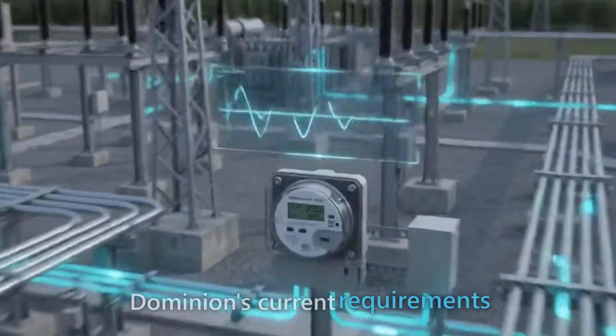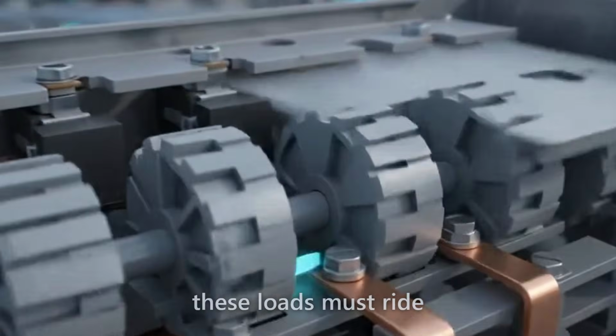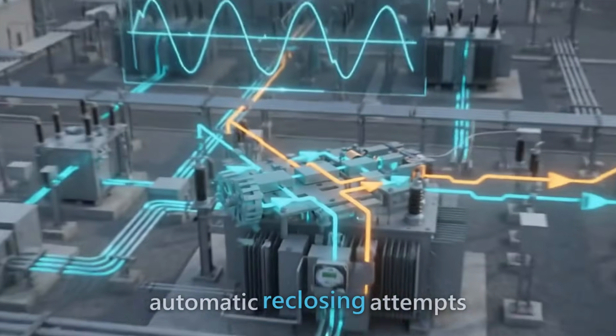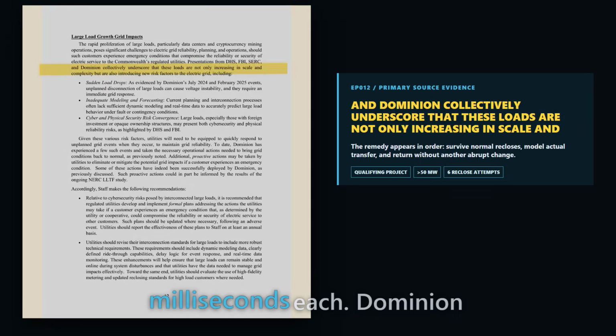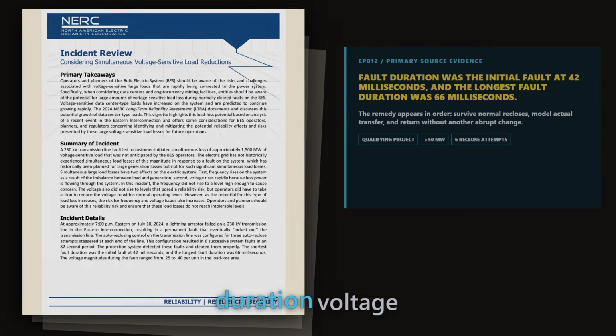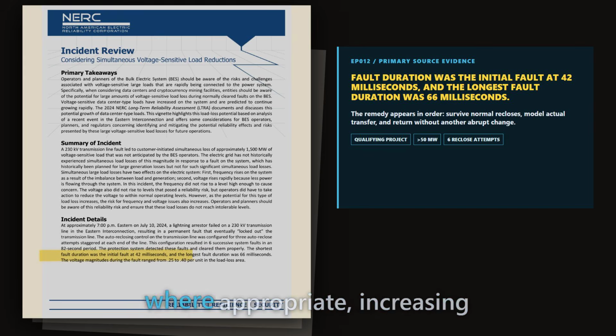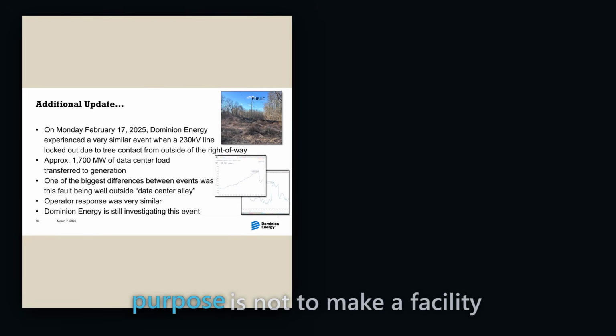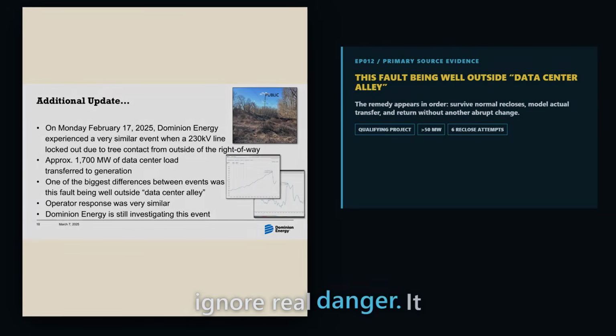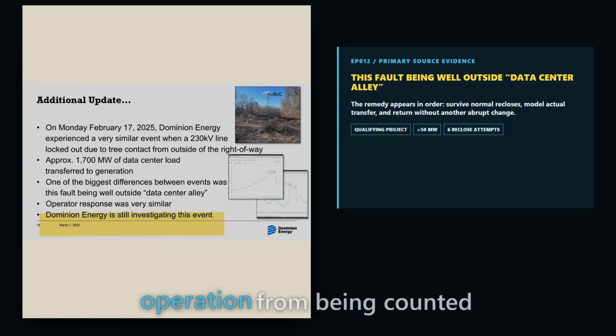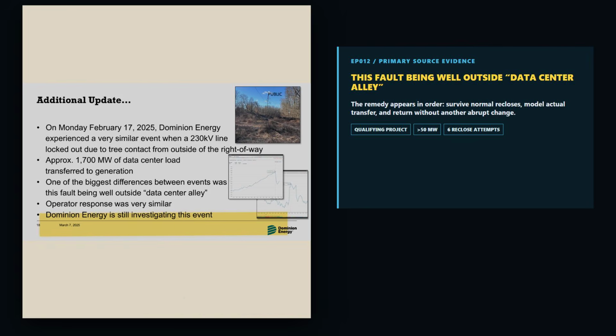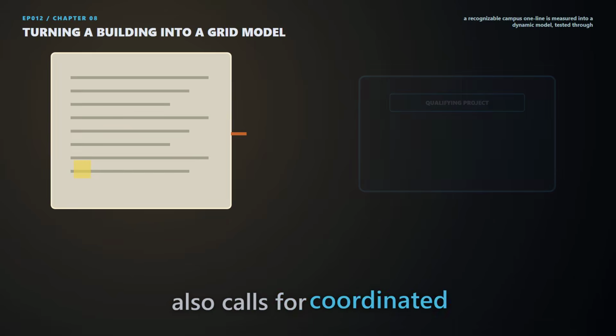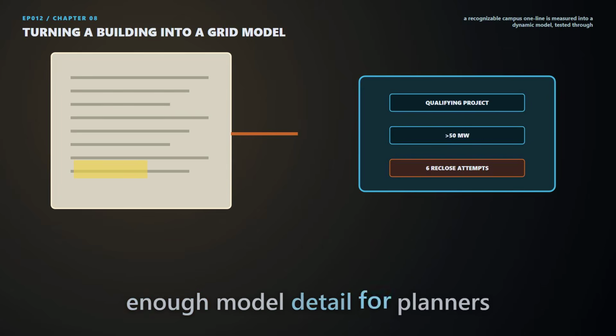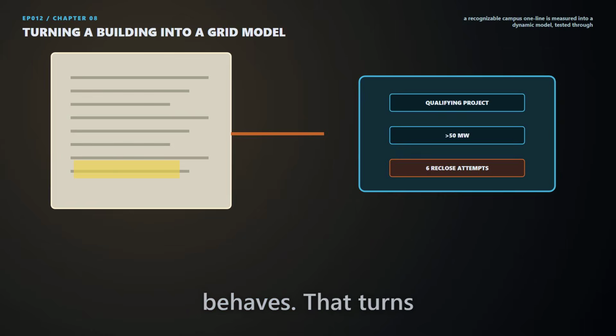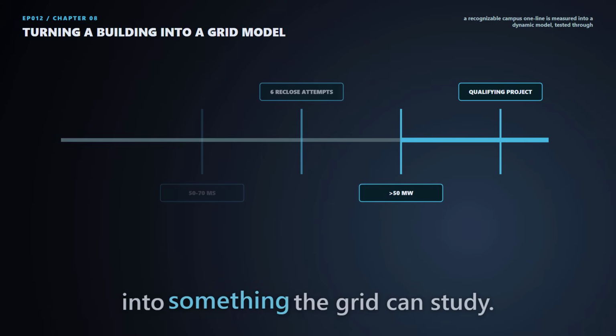Under Dominion's current requirements for qualifying projects, these loads must ride through at least 6 automatic reclosing attempts lasting 50 to 70 milliseconds each. Dominion recommends reviewing short-duration voltage detection timers and, where appropriate, increasing them to roughly 80 to 120 milliseconds or more. The purpose is not to make a facility ignore real danger. It is to prevent a normal breaker operation from being counted as several independent emergencies. The guidance also calls for coordinated protection settings and enough model detail for planners to test how the facility behaves. That turns an invisible customer decision into something the grid can study.